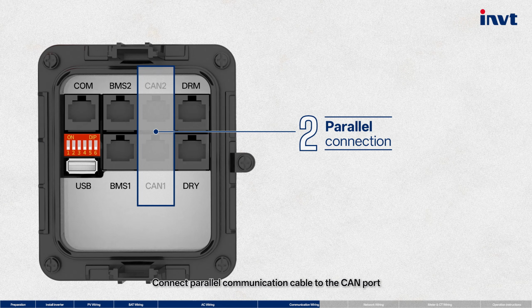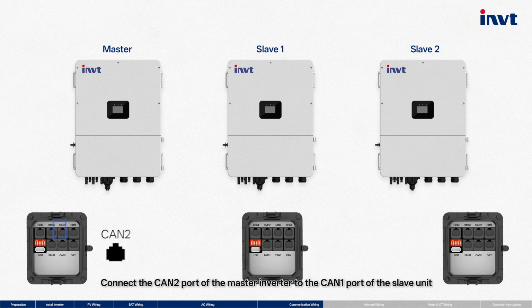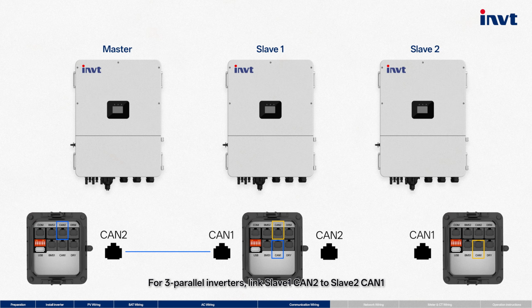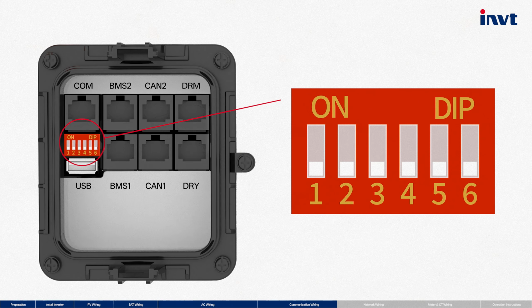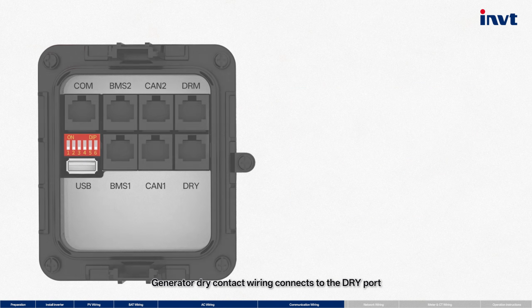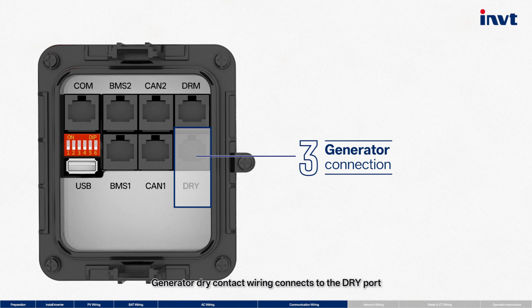Connect parallel communication cable to the CAN port. Connect the CAN 2 port of the master inverter to the CAN 1 port of the slave unit. For 3 parallel inverters, link slave 1 CAN 2 to slave 2 CAN 1. Toggle DIP switches 1 and 2 to on position. Generator dry contact wiring connects to the dry port.